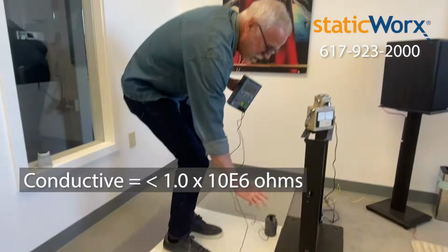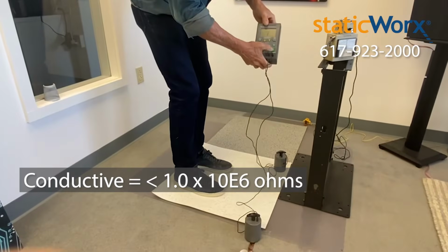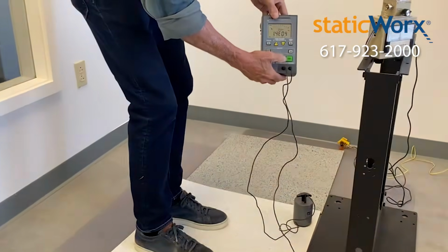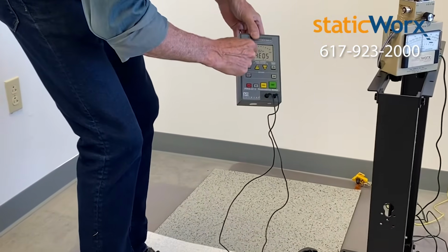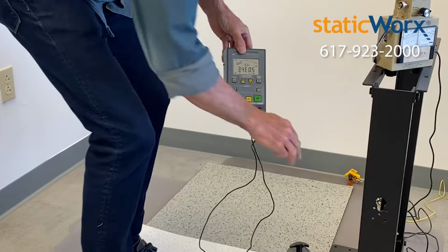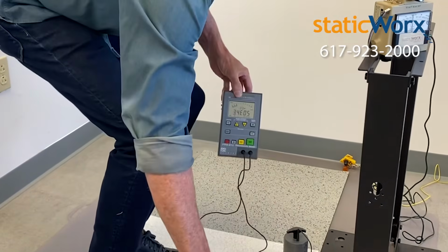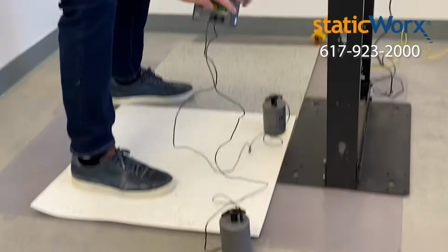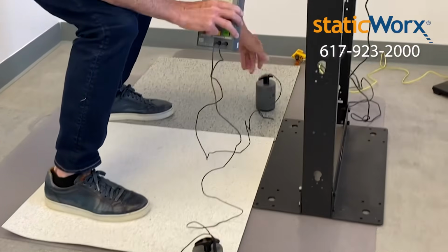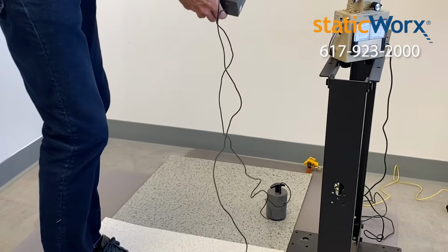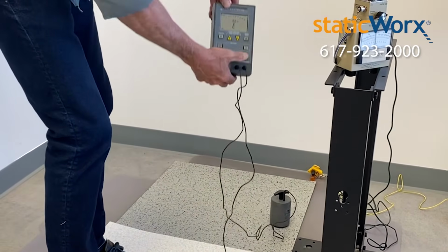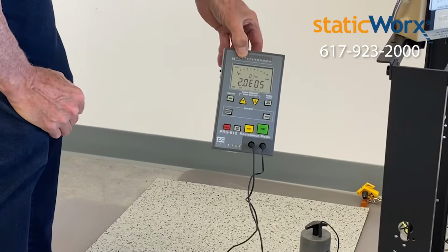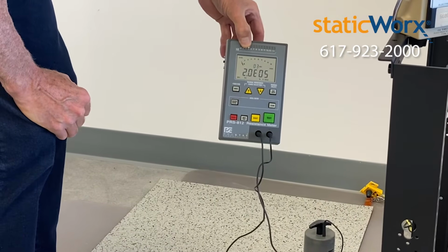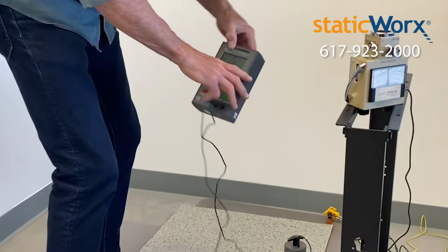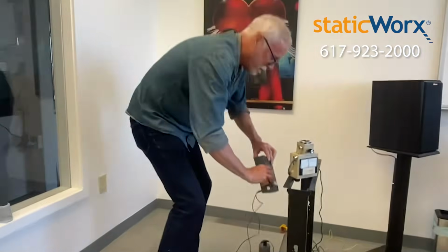This is a conductive vinyl floor. When I test this, I'm measuring a resistance of 3.4 times 10 to the fifth from this probe to the groundable point. Now I'm going to move the probe to the conductive rubber floor. I'm going to hit a reset button, and I'm measuring 2.0 times 10 to the fifth. So both of these floor tiles measure in the 10 to the fifth range.